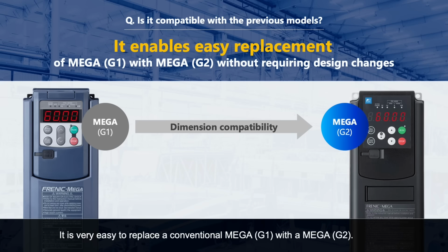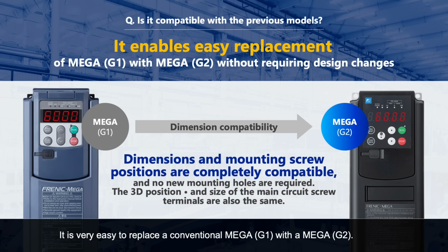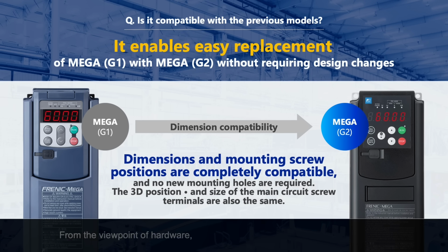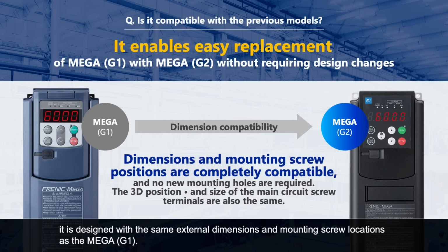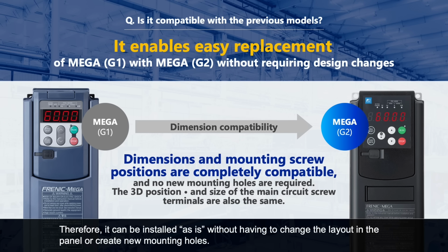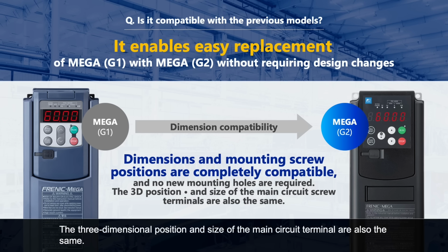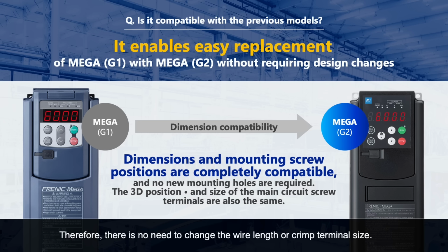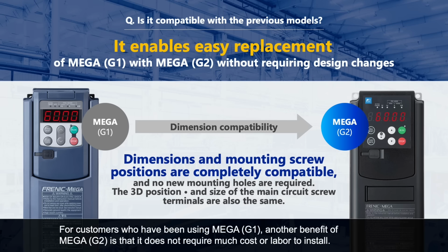It is very easy to replace a conventional Mega G1 with a Mega G2. From the viewpoint of hardware, it is designed with the same external dimensions and mounting screw locations as the Mega G1. Therefore, it can be installed as is without having to change the layout in the panel or create new mounting holes. The three-dimensional position and size of the main circuit terminal are also the same. Therefore, there is no need to change the wire length or crimp terminal size. For customers who have been using Mega G1, another benefit of Mega G2 is that it does not require much cost or labor to install.